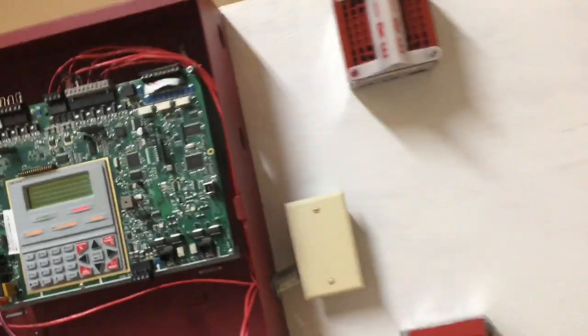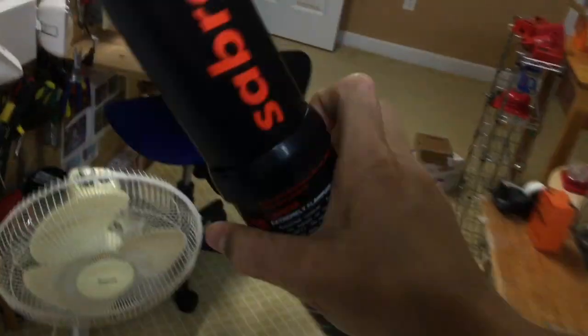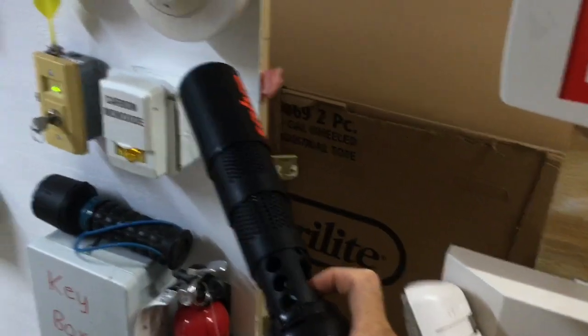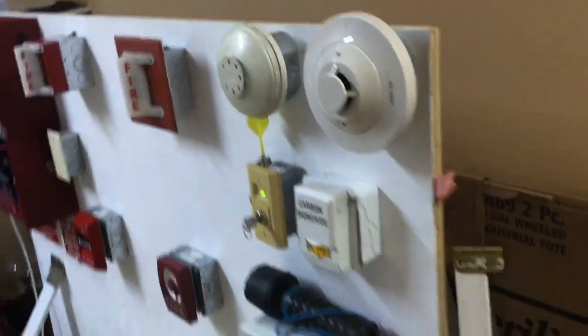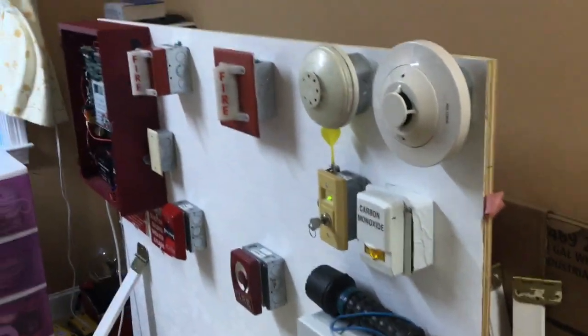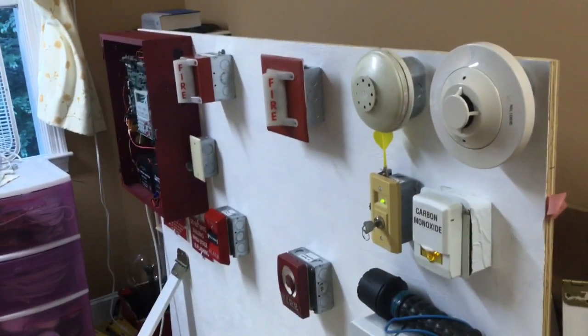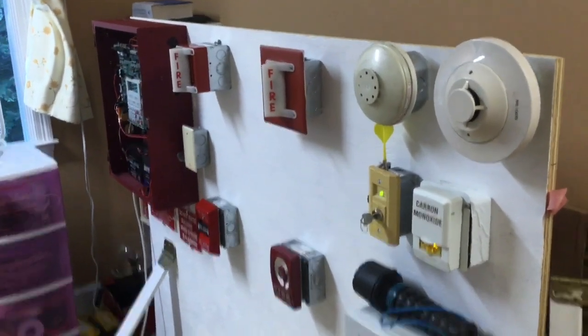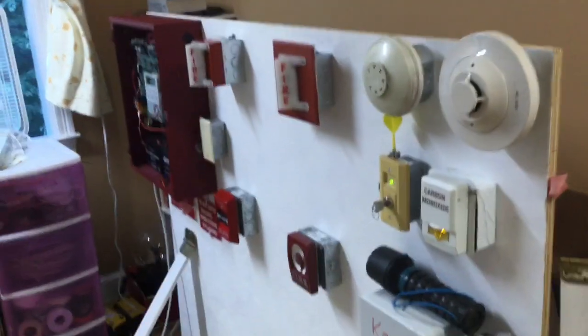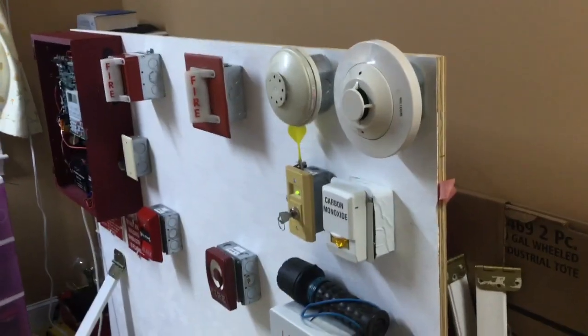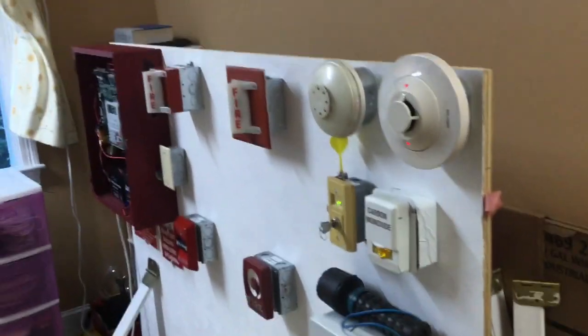All right, so finally I'm going to smoke out the detector and we're going to set the system on continuous, because who does not love continuous. Get that Smoke Sabre out, and then I'm going to aim it at the detector. Shake it a little first. That should be plenty. It takes a little while. I'm just going to talk while I'm waiting for it to go off. So that detector actually came - oh wow!